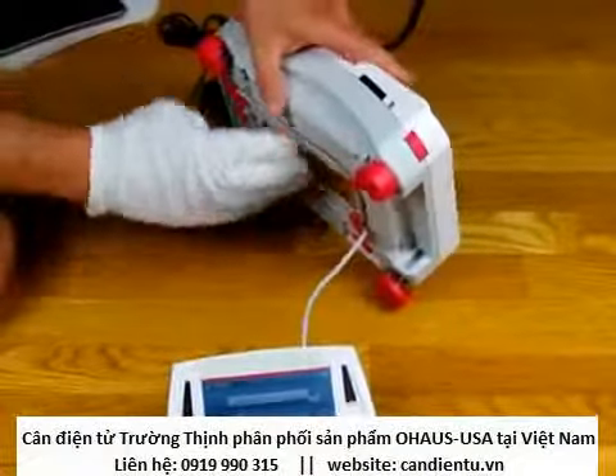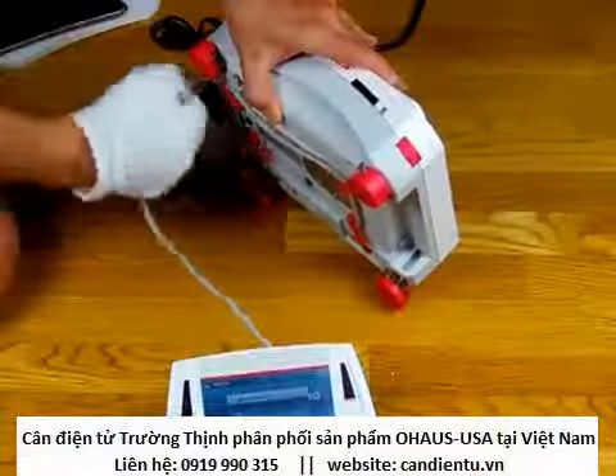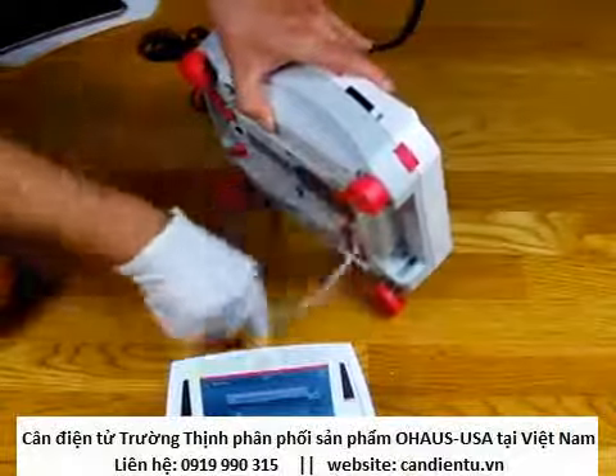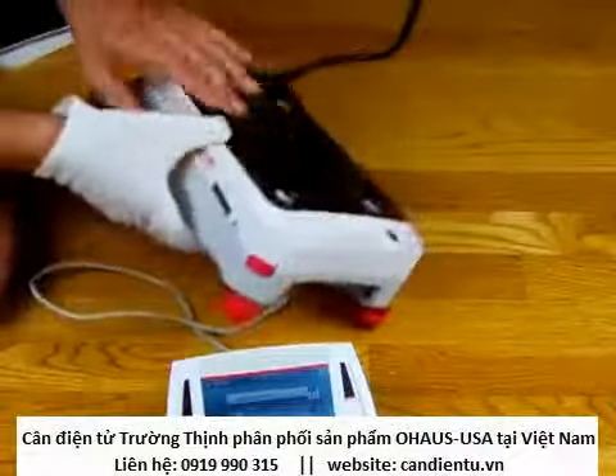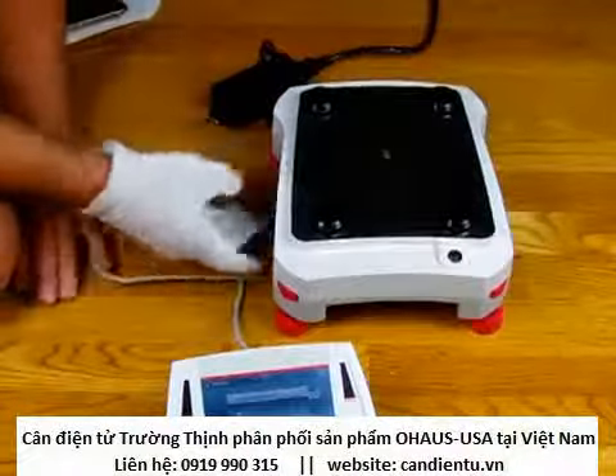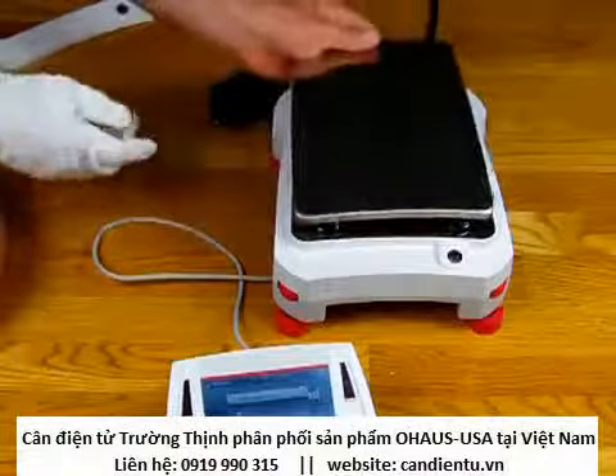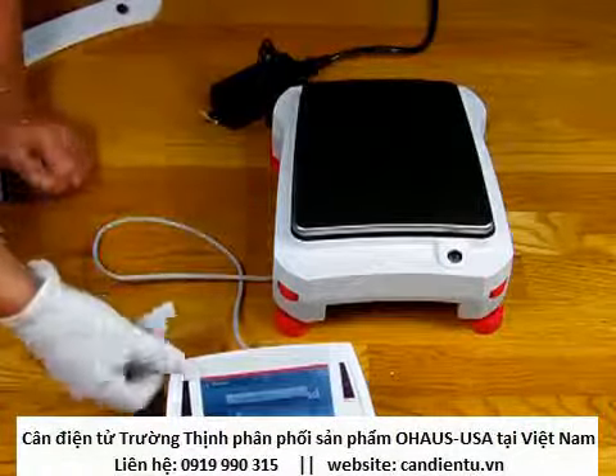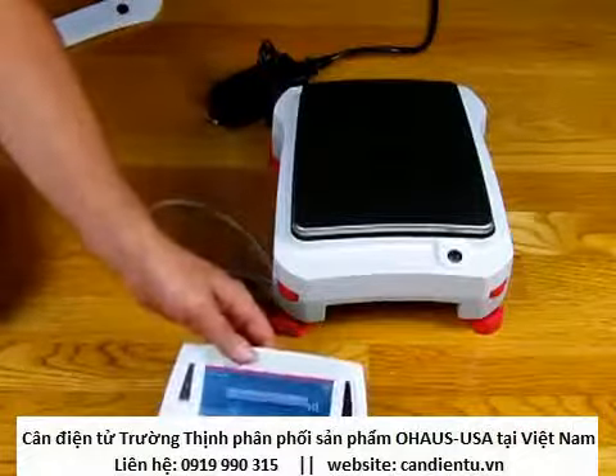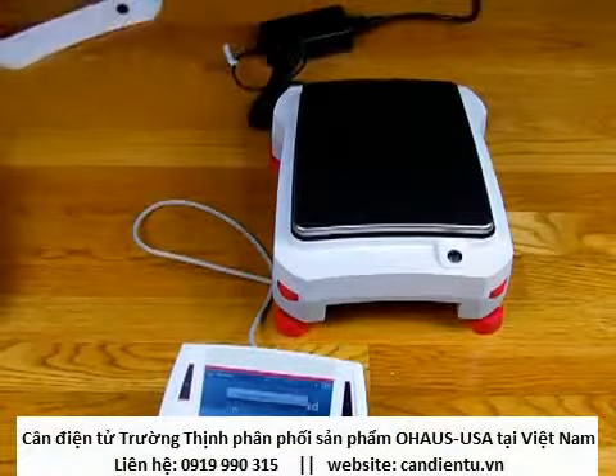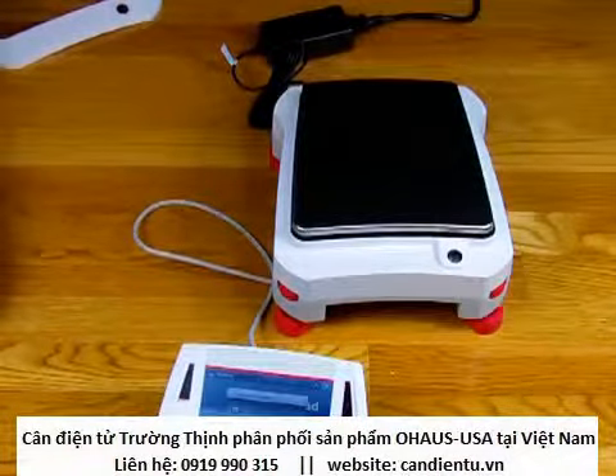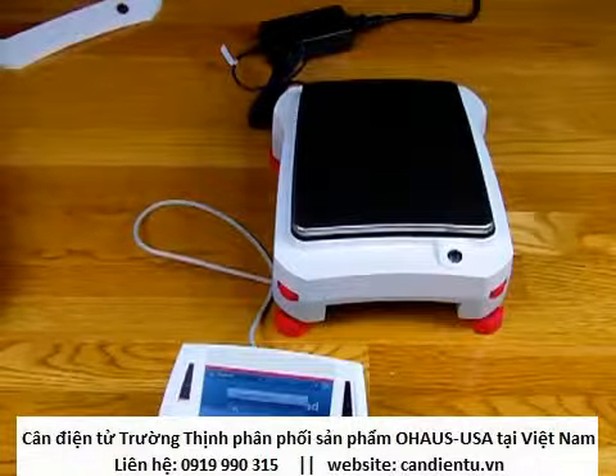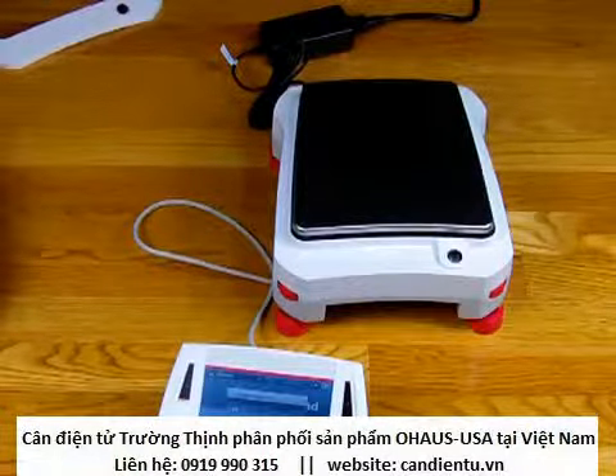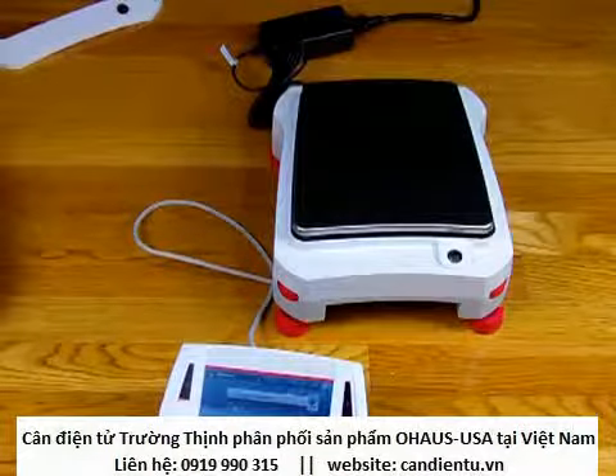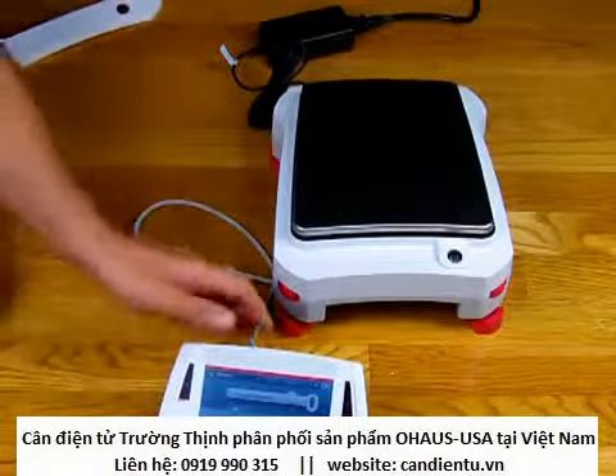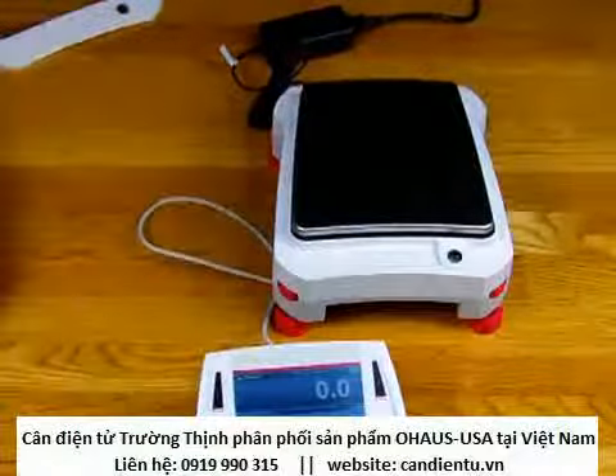On the bottom of the balance, we simply undo the cable, and we have the ability to move the head wherever we want. Just as I did that, the balance automatically goes out and does a calibration - it senses any temperature change and will automatically perform the internal calibration. And now the balance has just calibrated.